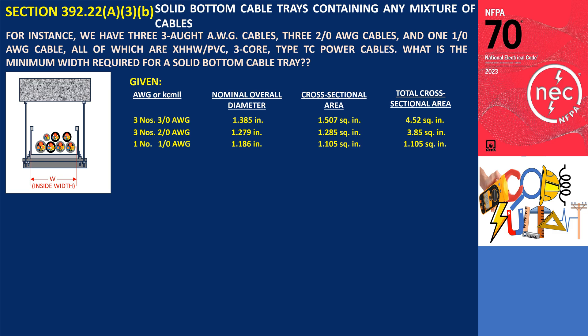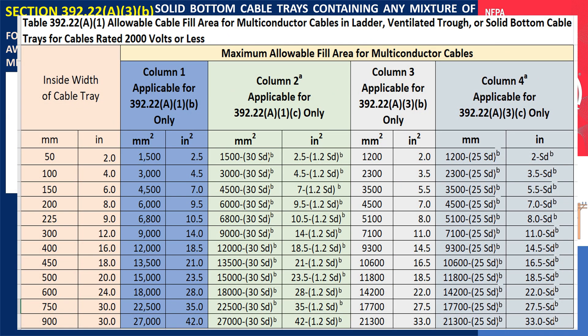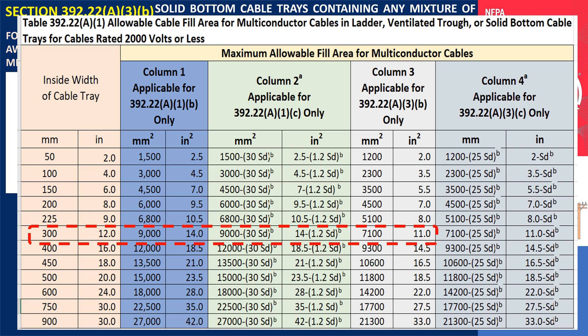The procedure for calculating the cross-sectional area was shown in my previous video. Adding these together, the total cross-sectional area of all the cables is 9.48 square inches. Since a 225-millimeter (9-inch) solid-bottom cable tray has a maximum capacity of 8 square inches, the minimum inside width required for the solid-bottom cable tray, as specified in Table 392.22(A)(1), Column 3, is 300 millimeters or 12 inches.